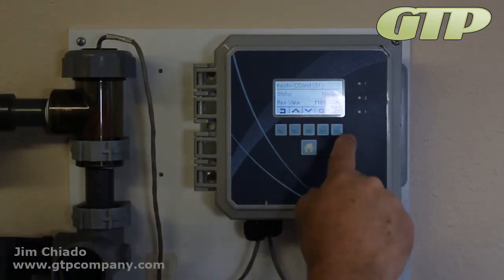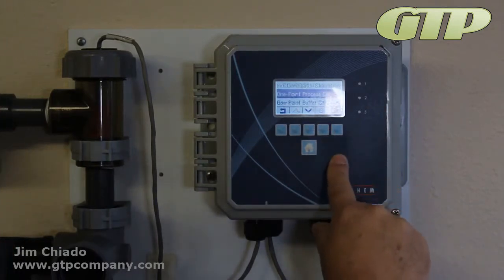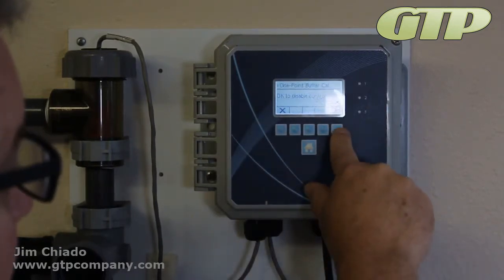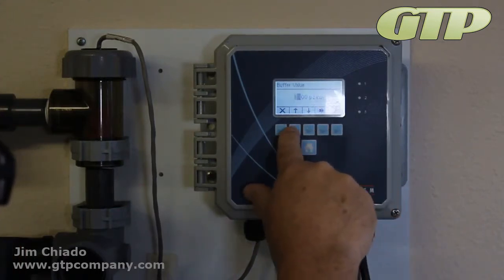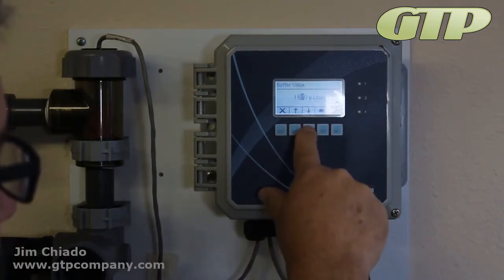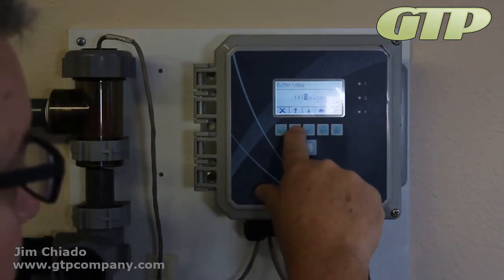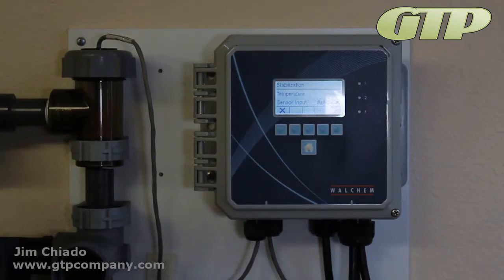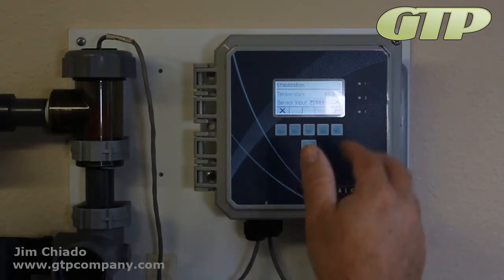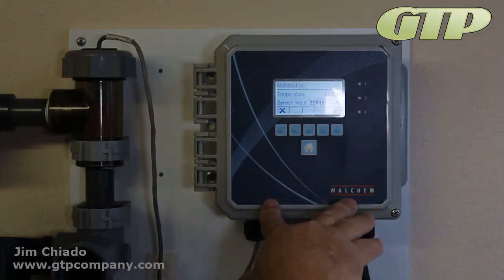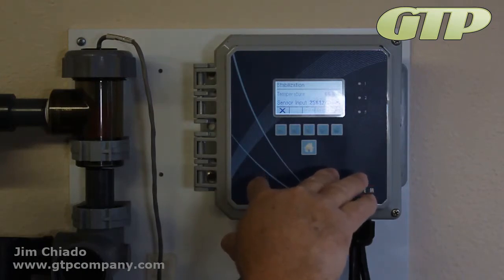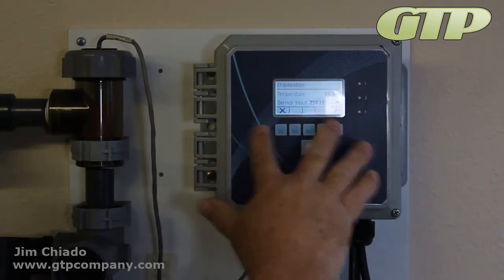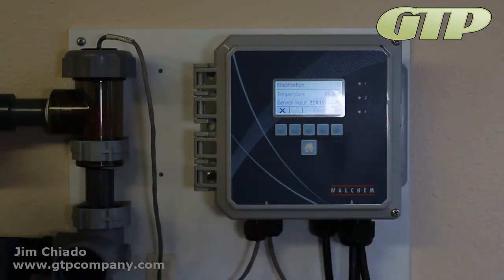So if I go to do a calibration, that button right there, 1 point buffer, disable the controls, and I'm going to tell it it's 1413. Now, if it wasn't within 1.5 times what it believed it was, 1180, it would never do the calibration. Here it is within that 1.5 times, and it should give me a stabilization. Please let it stabilize itself. If you hit the check, you can force a stabilization.